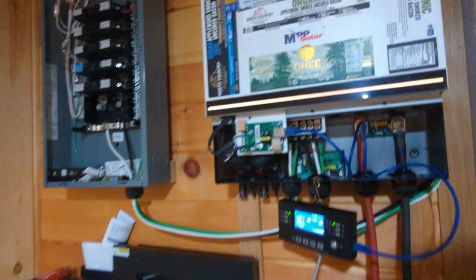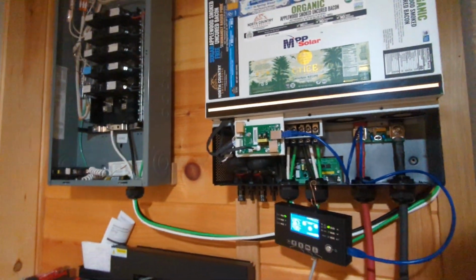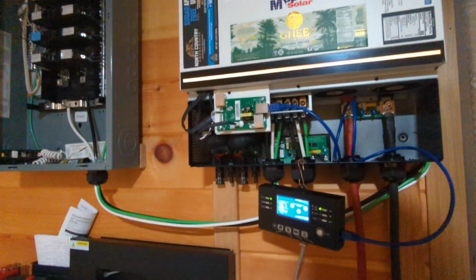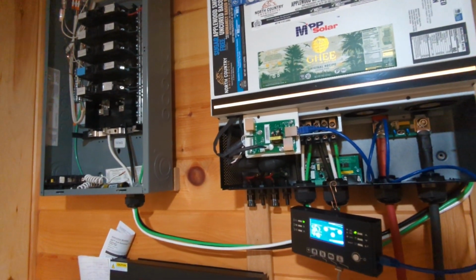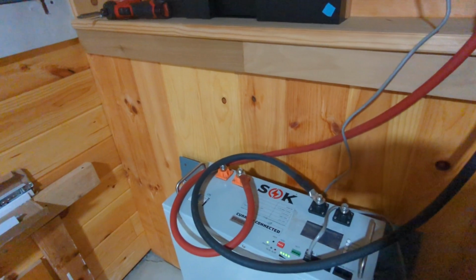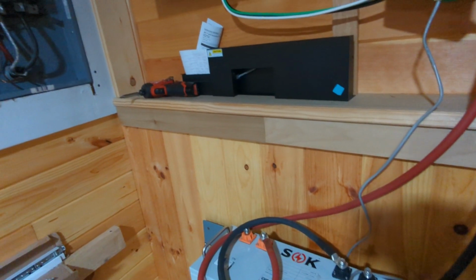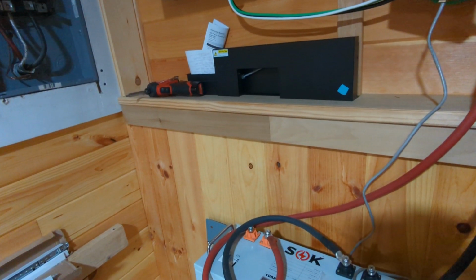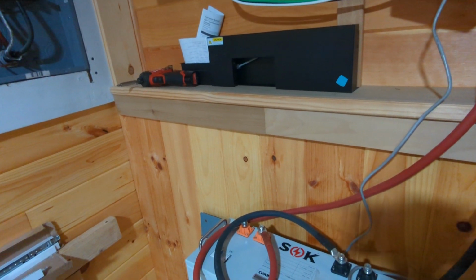So I am not able to use the full 6.5 kilowatts output from this inverter anyway. The neutral wire at 6-gauge is perfectly okay. If I do plan on changing batteries or adding more batteries, I will change that 6-gauge neutral wire to 4-gauge to match the black hot wire.